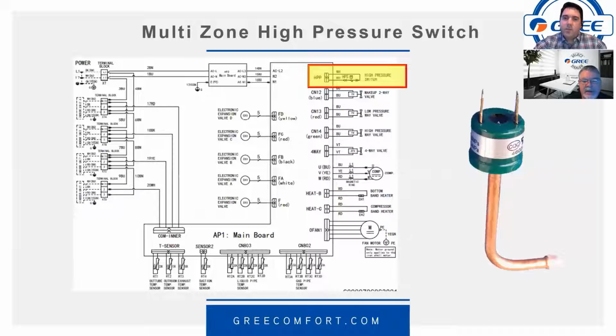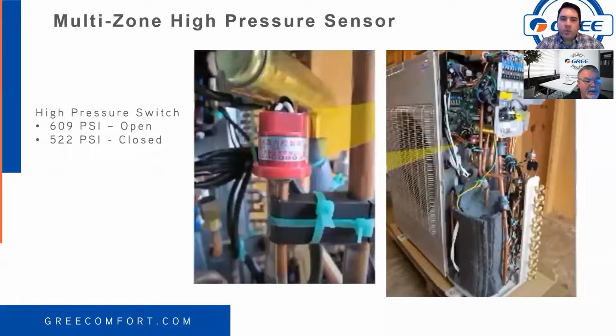So let's see. This is what it looks like. Again, the board diagram showing you where the high pressure switch is at. If you're curious whether or not a system has a high pressure switch, this is a good way to figure it out. Look at the board diagram. This thing trips at over 600. 609, the switch opens. 522, it closes back. And this is where it's located. It's off the compressor discharge line. Should be pretty easy to find. That's what it looks like.